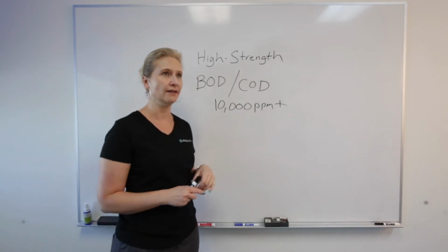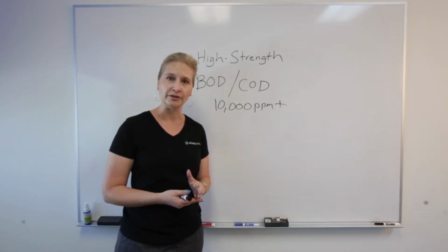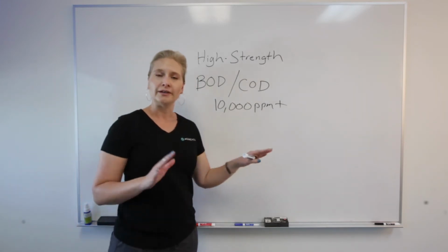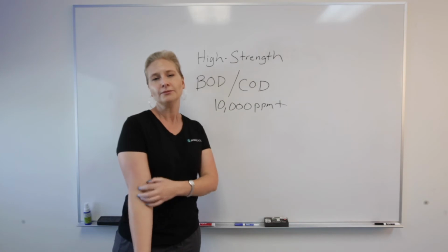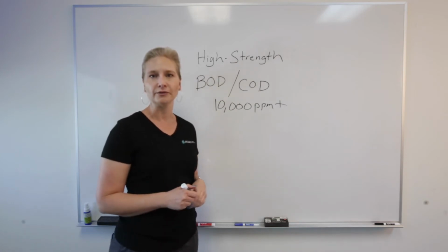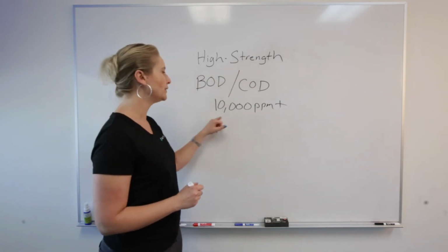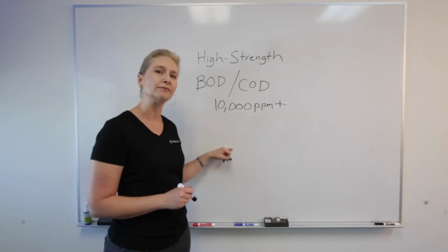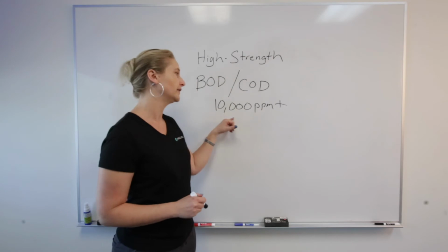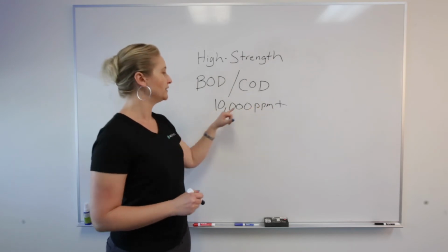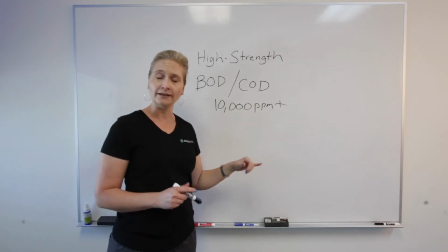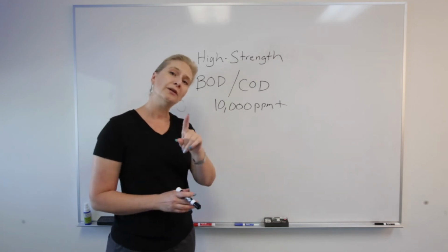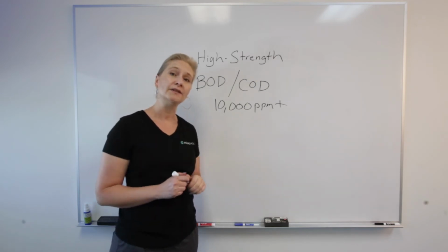Now, in order to be cost effective in doing this industrial pretreatment, right, you want to make sure that you can separate your stream efficiently, because probably most of the time in your manufacturing process, most of your water is not going to be 10,000 or more. Most of your water is going to be on the lower spectrum. But some of your processes are going to discharge somewhere up of 100,000 parts per million, and then that's going to mix in with the rest of your flow and start causing problems. So what about isolating those specific processes?